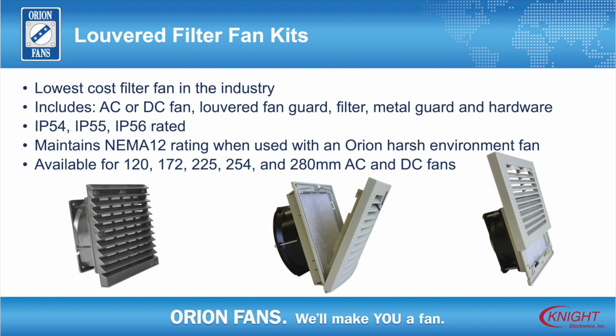When louvered filter fan kits are used with harsh environment fans, the system can be rated to IP54, IP55, IP56, and/or NEMA 12 standards. Different fan models have NEMA insulation ratings of either Class B for PBT plastic fans or Class F for metal fans, allowing for higher fan operating temperatures.